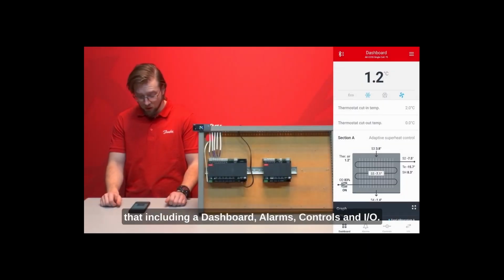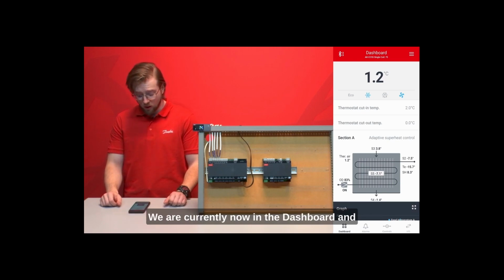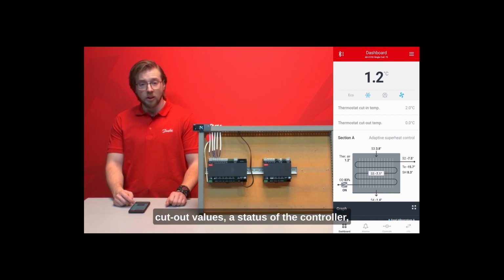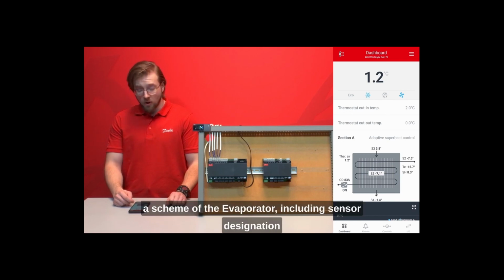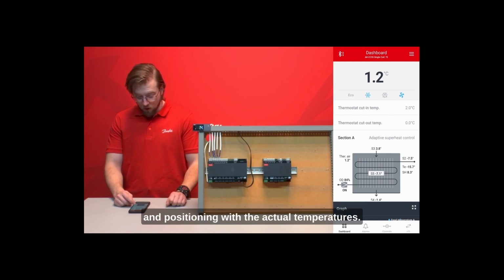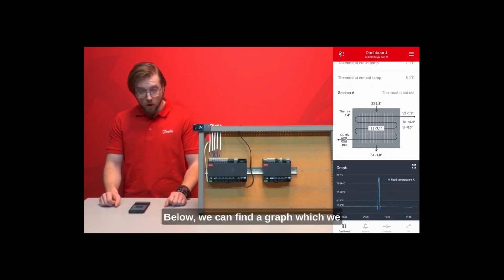The app is made of 4 large menus that include a dashboard, alarms, controls and I/O. We are currently in the dashboard, and here we will find all the important information such as the thermostat air temperature, cut-in, cut-out values, the status of the controller, a scheme of the evaporator including sensor designation and positioning with the actual temperatures. Below we can find a graph which we will come back to in a moment.